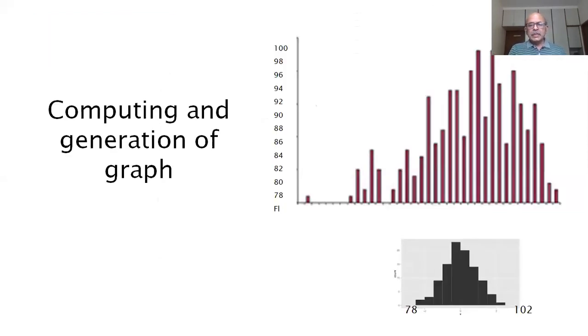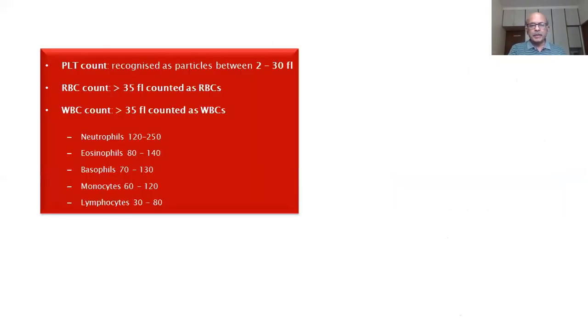And based on this, the computer graphically tells you the total number of cells and the total number of cells of various sizes. So this is known as a histogram, which is what this computer calculates based on the graph which is available for it. And when the counter first starts counting, in the first chamber, what is counted is the platelet and RBC together.